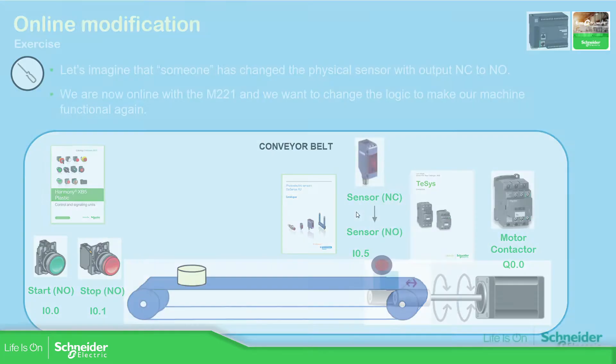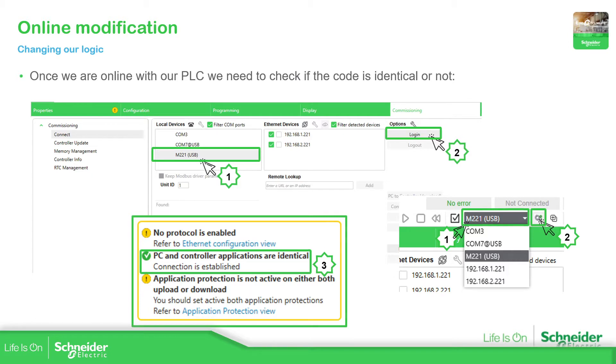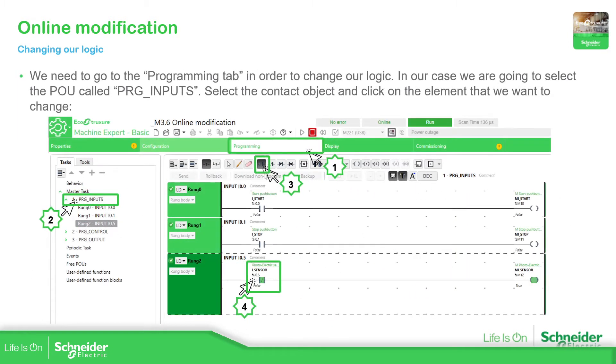So what we need to do basically is to connect to the PLC, be online, see if we are using the latest application, then modify the logic, replace the normally closed contact for the normally open and then send the new application while we are connected.